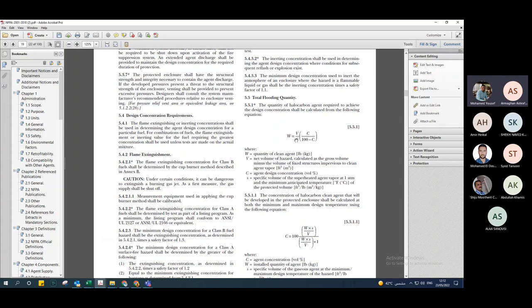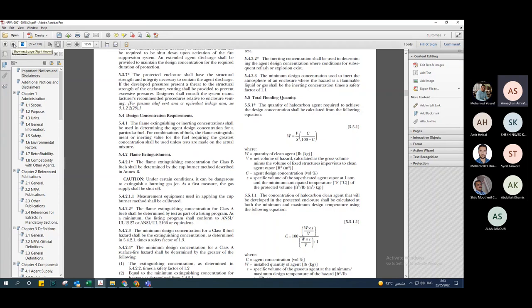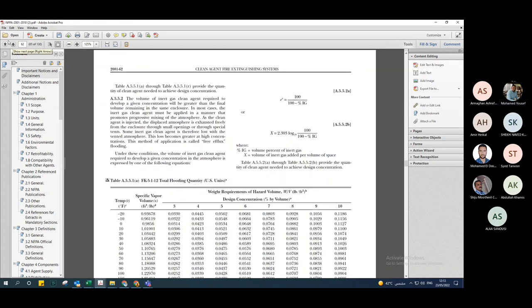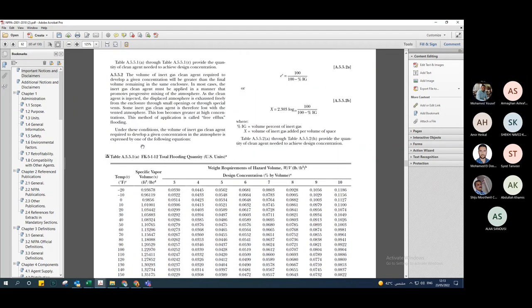Now I need to go to S — the specific volume. If I go to page number 62 for the Novec system in NFPA 2001, I will find table A.5.5.1 for FK5-1-12 total flooding quantity. This table shows temperatures from −20 up to 40°C with their corresponding specific volumes.